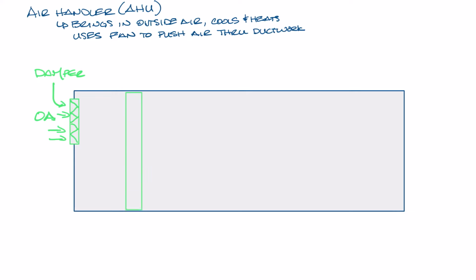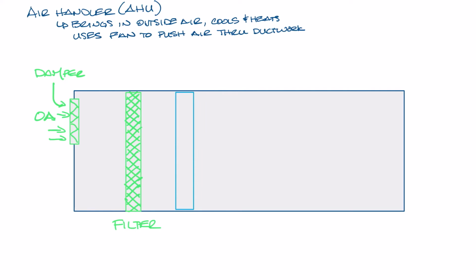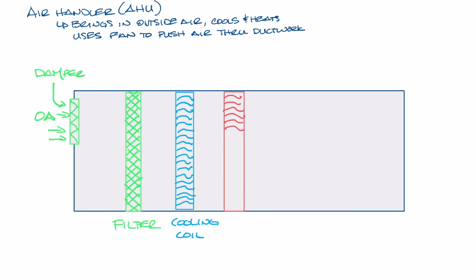Next, the air passes through the filter. You want to filter the outside air before it passes through the water coil so that you don't deposit anything on the water coils. You don't want your water coils to become your filters by catching stuff on the surface of the coils, which will reduce their efficiency. Next, the air will pass through cooling and heating coils. The cooling coils cool the air down and the heating coils warm them up. I'll cover whether the cooling coil or heating coil should be first in a future video.